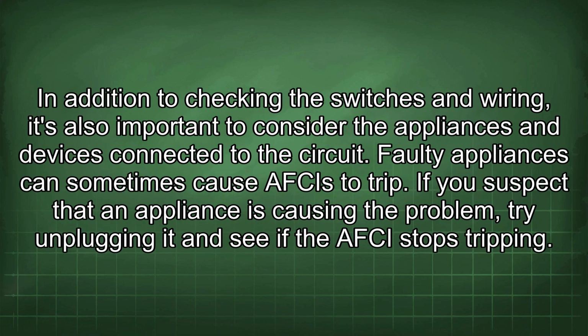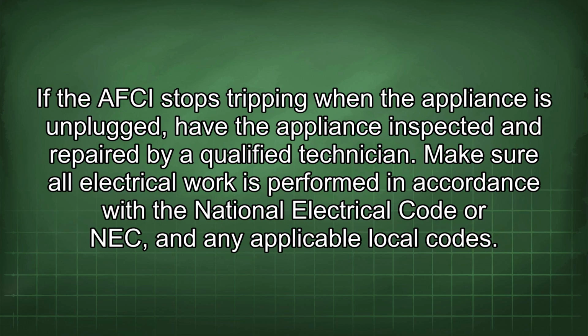home. In addition to checking the switches and wiring, it's also important to consider the appliances and devices connected to the circuit. Faulty appliances can sometimes cause AFCIs to trip. If you suspect that an appliance is causing the problem, try unplugging it and see if the AFCI stops tripping. If the AFCI stops tripping when the appliance is unplugged, have the appliance inspected and repaired by a qualified technician.